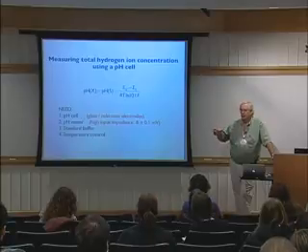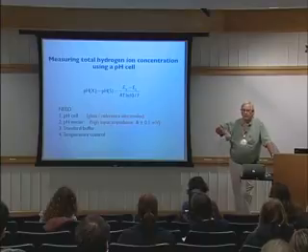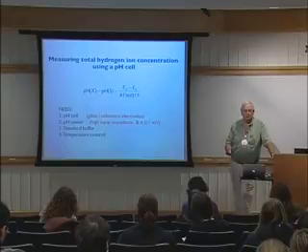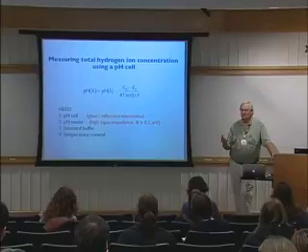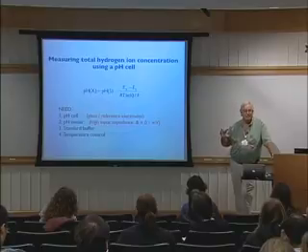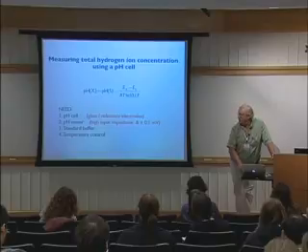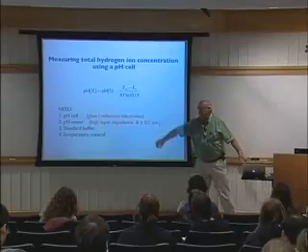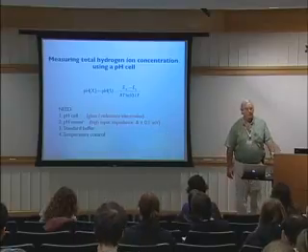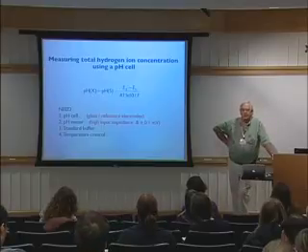If you want to measure the potential of that, you've got to have a circuit that can do that without putting much current around the circuit, because if you put current on the circuit, you electrolyze the water right at the surface of your electrode. The pH changes right where you're electrolyzing the water, and you get the most interesting results, but probably not the ones you were hoping for. So a pH meter is a high input impedance system, and you probably want it to read to plus or minus 0.1 of a millivolt. Can you really rely on the data at that level? Hell no.